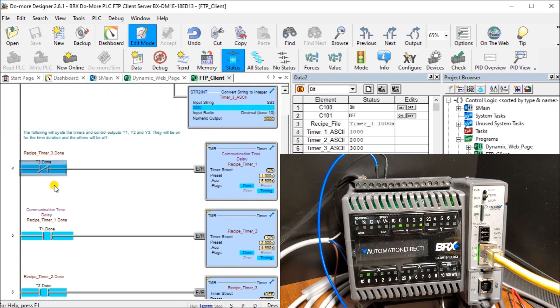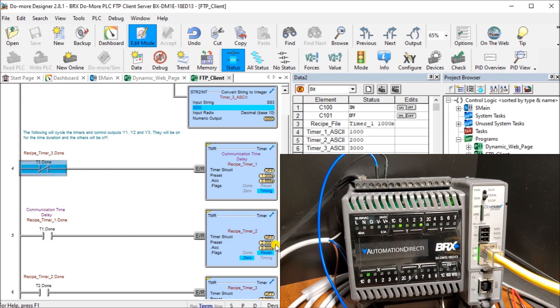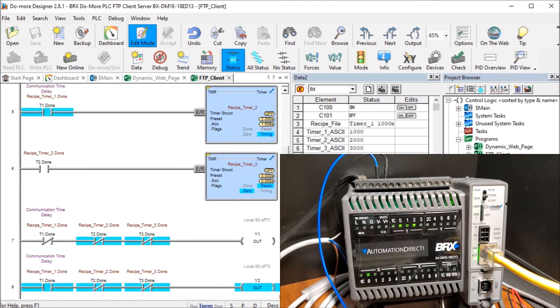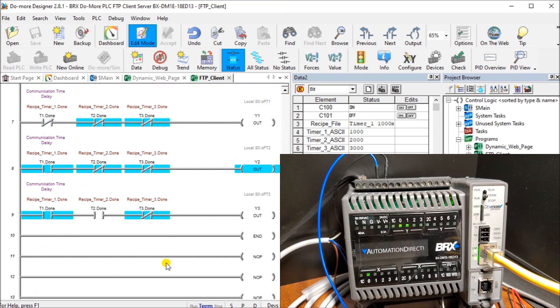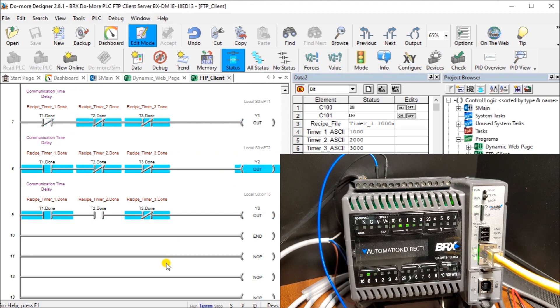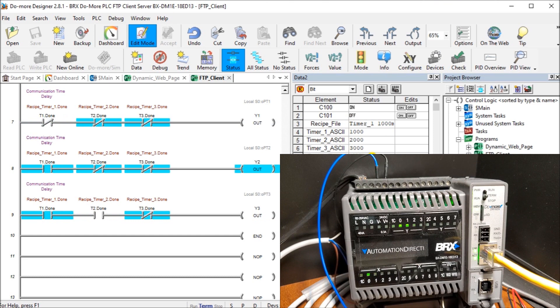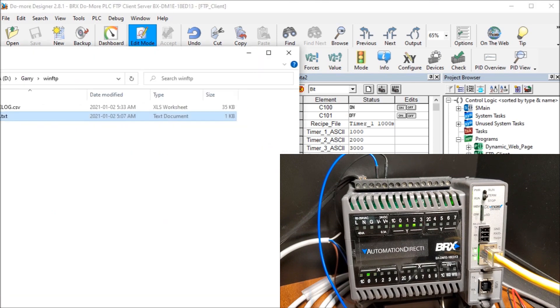Then what we have is a simple program that we're timing up different timers. If timer three is not done, then we activate timer one. When timer one's done, it activates timer two. Timer two done, we activate timer three. Then it repeats again. So the actual output will cycle. One is on for one second. Two is on for two seconds. Output three is on for three seconds, based on our time values that we see here.